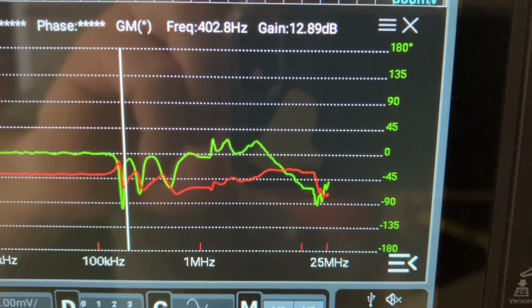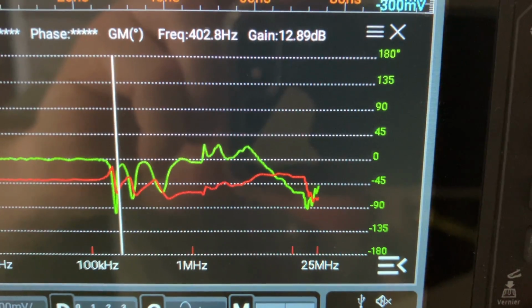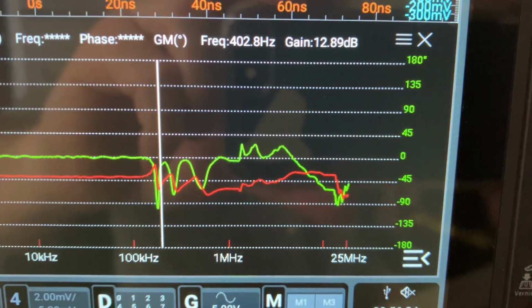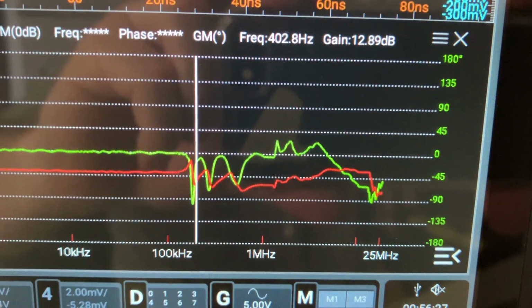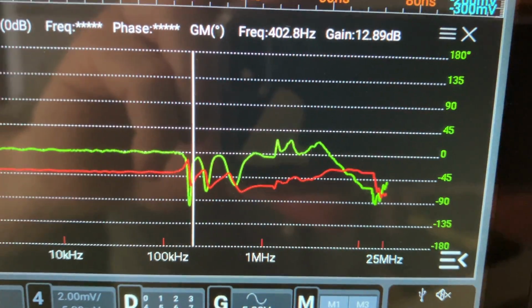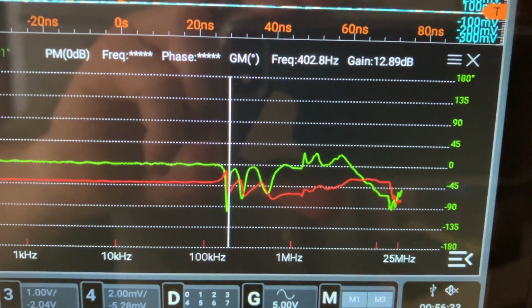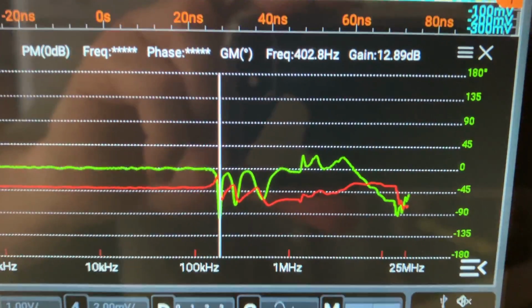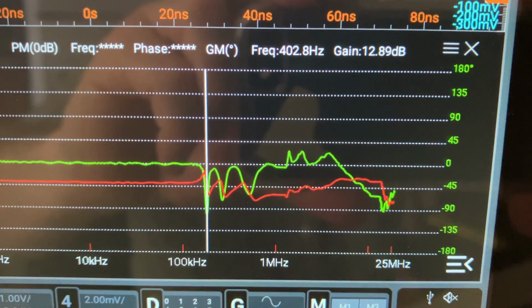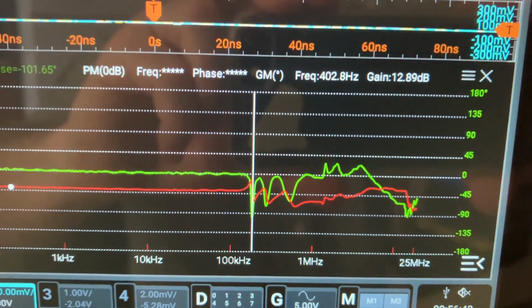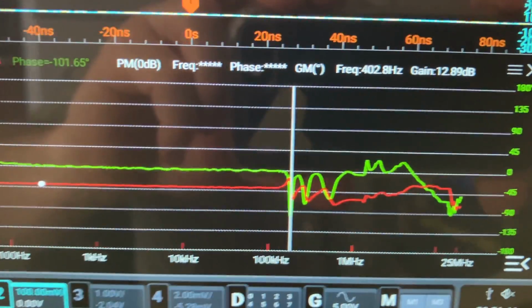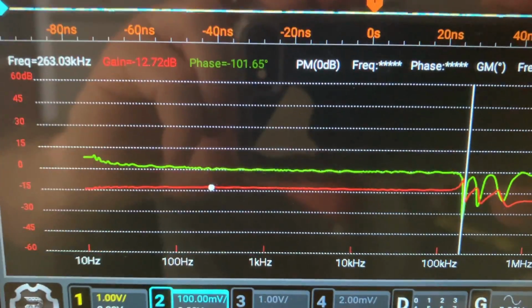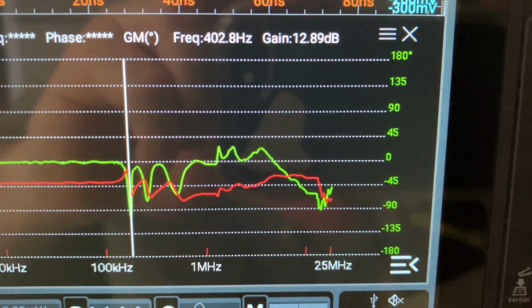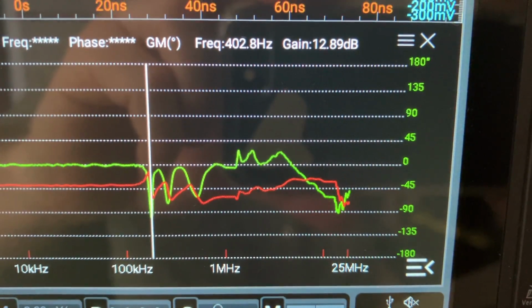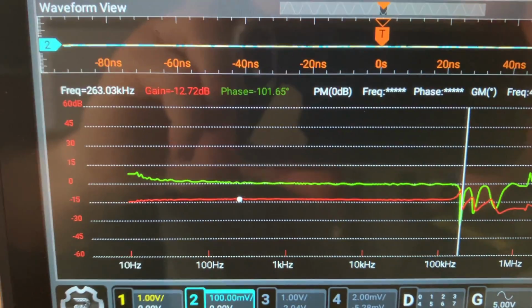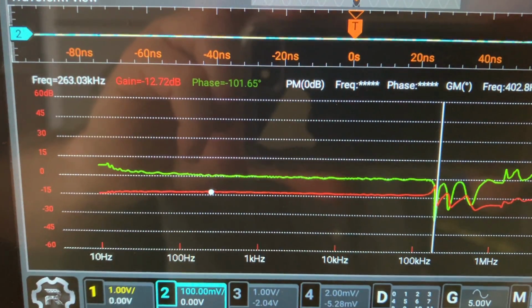At 25 meg again, the frequency collapses at, let's say, 22, 21. But the phase does not go all around the place. It stays around 0 except for the small peak at the frequency. If I put the cursor there, this is probably the maximum that you want. It's 90 degrees phase, but it recovers very fast after that first resonance. So it's still useful beyond that a little bit. The amplitude, the red line, is staying around the same gain from the beginning, so it's not too bad. So basically, you could work up to 260 kilohertz with this transformer.